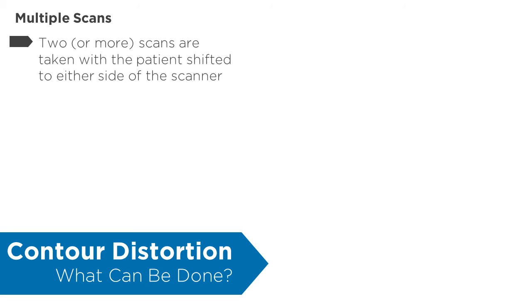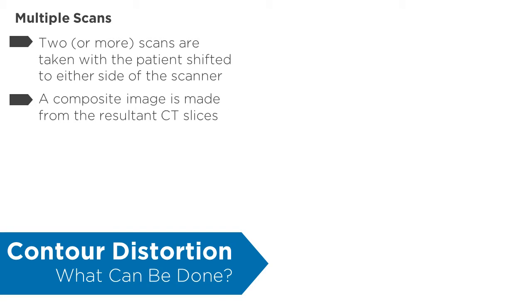Here are some common strategies for dealing with image distortion. Multiple scans can be taken with the patient shifted all the way to the left and to the right of the bore, so that each part of the region of interest is imaged within the scan field of view. A composite image can be made by putting together the undistorted parts of each CT slice.